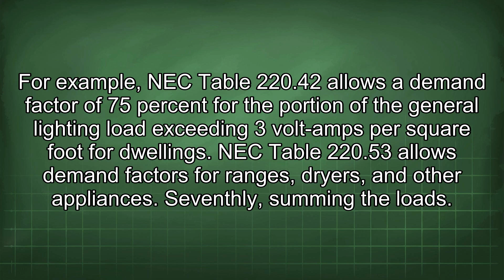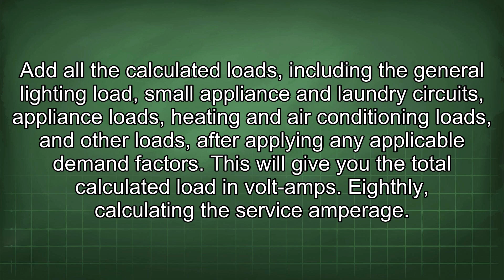Seventhly, summing the loads. Add all the calculated loads, including the general lighting load, small appliance and laundry circuits, appliance loads, heating and air conditioning loads, and other loads, after applying any applicable demand factors. This will give you the total calculated load in volt amps.